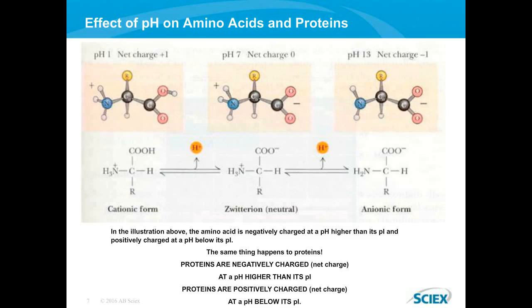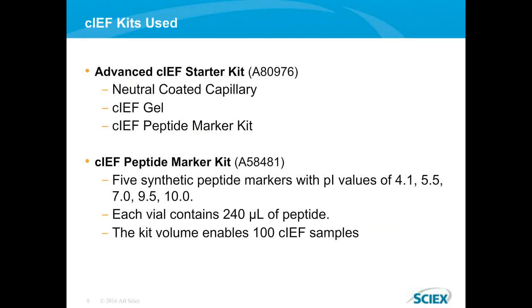On this slide I have the same amino acid at three different surrounding environments. In the center, this amino acid has a theoretical PI of seven. Therefore, when the surrounding pH is seven, the net charge is zero — it's focused to its PI. If I force that amino acid into a surrounding environment of lower pH than its PI, it carries a net positive charge. The opposite is true when forced to a more basic environment — its net charge is then negative. The SCIEX cIEF method takes advantage of this natural process to focus your sample into a pH gradient and determine its predicted PI. The current profile starts between 14 to 18 microamps, then decreases rapidly, almost down to zero. When it stays just above zero, we know the focusing step has completed — indicating all proteins, peptides, PI markers, and the pH gradient have formed.